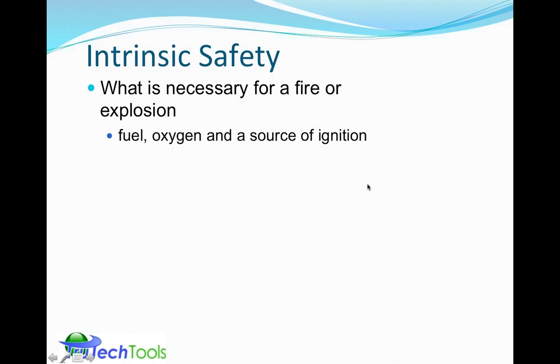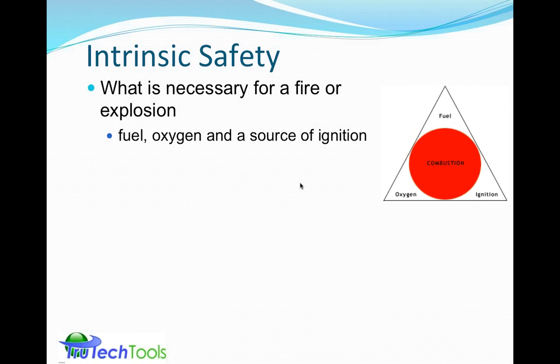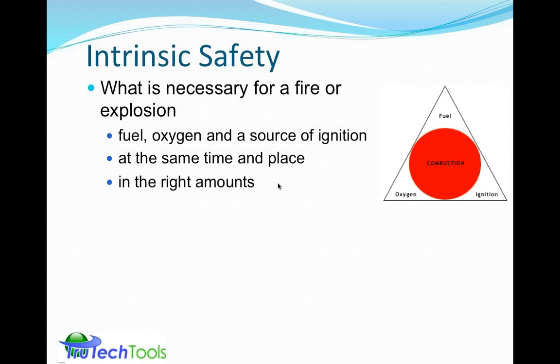So what's necessary for an explosion or a fire or the combustion of gases or fuels? Basically, you need fuel, oxygen, and a source of ignition. Yesterday, I gave the Combustion 101 seminar, and we talked about that from a different aspect, but we're still talking about the same process, the combustion triangle, if you will: fuel, oxygen, and a source of ignition. The quantities, the amounts of oxygen and fuel have to be correct or within certain ranges, and the amount of energy present in ignition must be within a certain range for the mixture in order for combustion to take place. So it's a right place, right time, right amount kind of situation.